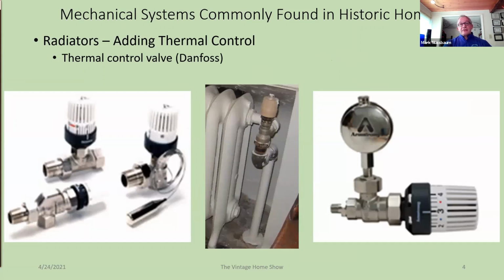If you want to add some thermal control to those radiators, if you're having trouble with overheating in spaces, one of the things you can do is add a thermal control valve. Danfoss is one of the manufacturers. It's a little thermostatic head, non-electric, all mechanical. On two-pipe radiators, you replace the control valve with this, and then you just dial it hotter or colder. You can get it with remote sensors if it's an enclosed radiator. If it's a single pipe radiator, you can still control it, but you take that automatic air vent off the side, install this part of the valve controller, and then put the vent valve back onto the side of this controller.